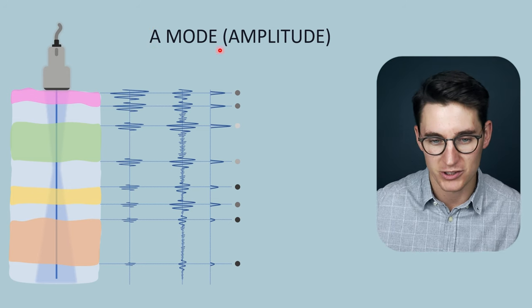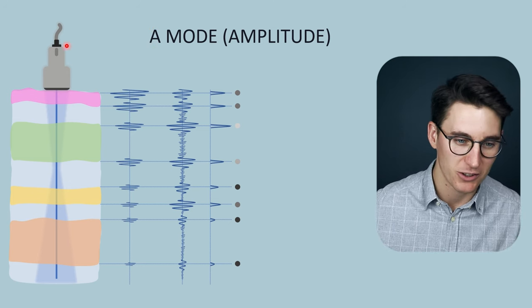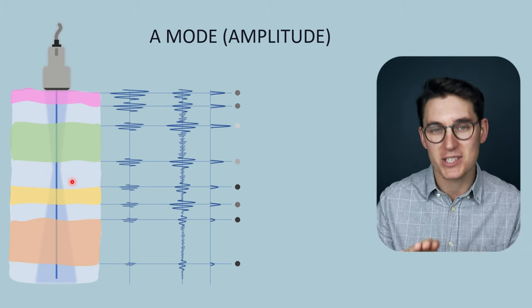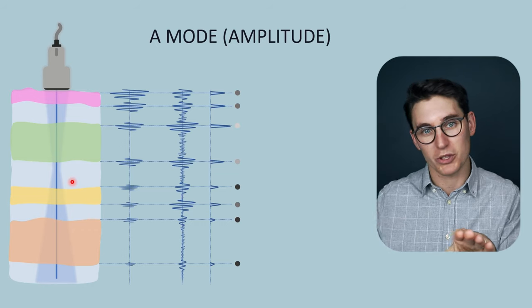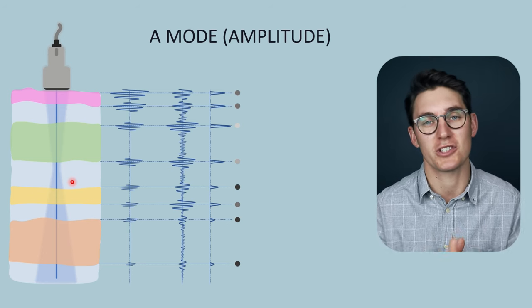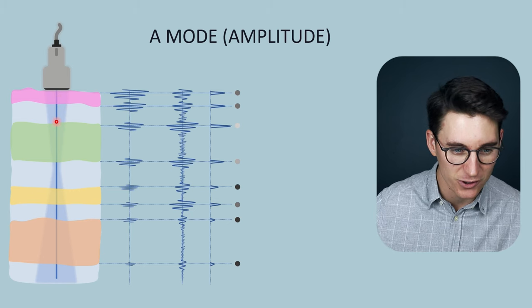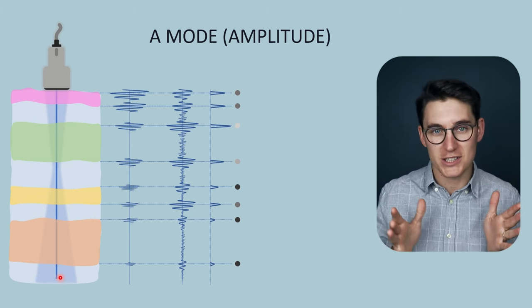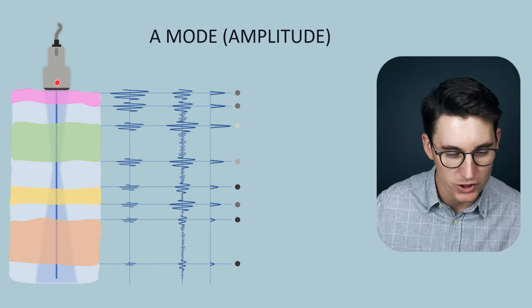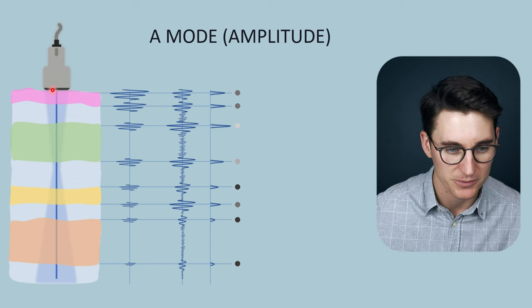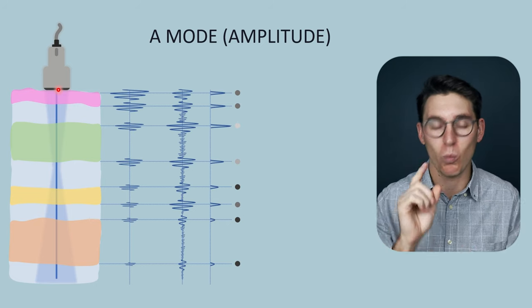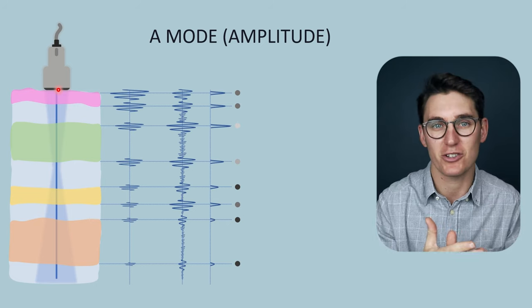A stands for amplitude, and you'll see why that's important. We place our ultrasound machine on the patient's tissue, which has various tissues of differing acoustic impedances. It's those differences in acoustic impedances at tissue boundaries which determine how much of the incident wave will reflect back towards our ultrasound machine and how much will be transmitted through. In A-mode we take a single line — we are not scanning an entire broad field. We have one transducer element firing and receiving those signals, and we are receiving those echoes as one signal.